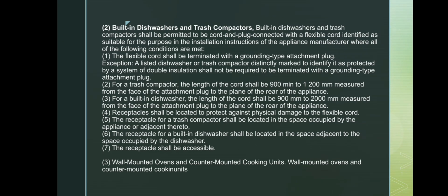Next, we have the rules for built-in dishwashers and trash compactors that use flexible cords. These appliances may be cord and plug connected if the manufacturer approves it and if all conditions are followed. First, the flexible cord must end with a grounding type plug unless the unit is listed as double insulated, in which case a grounding plug is not required.